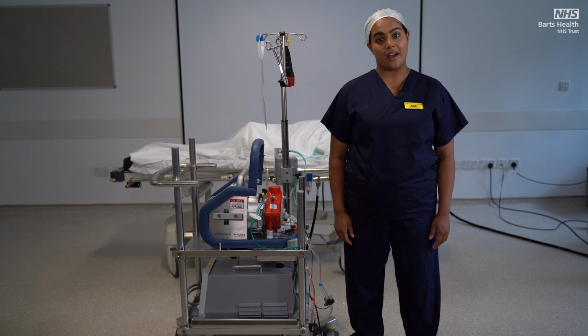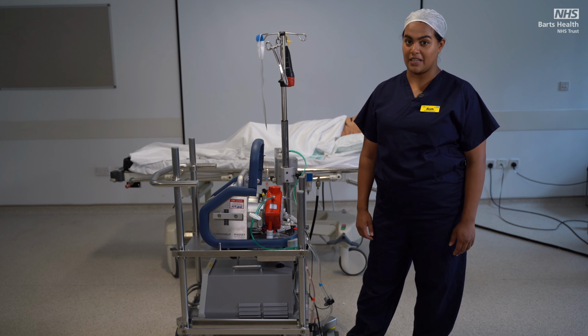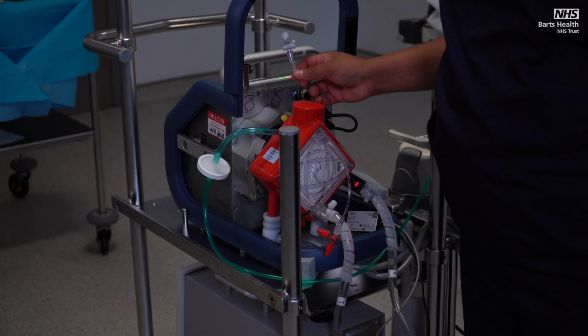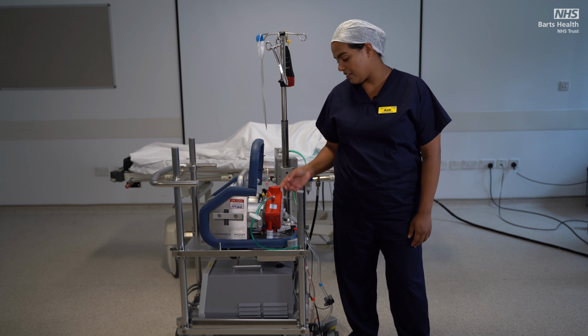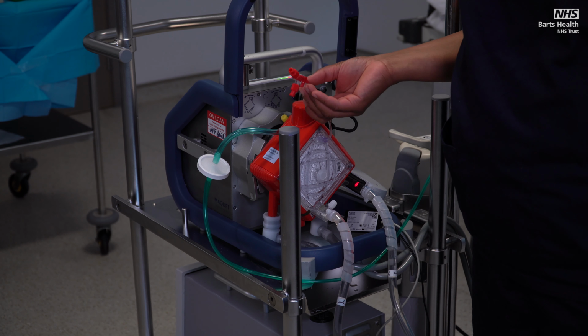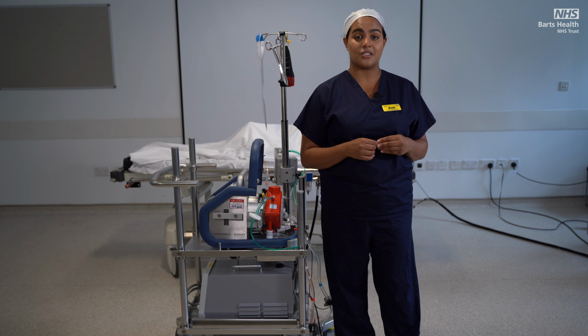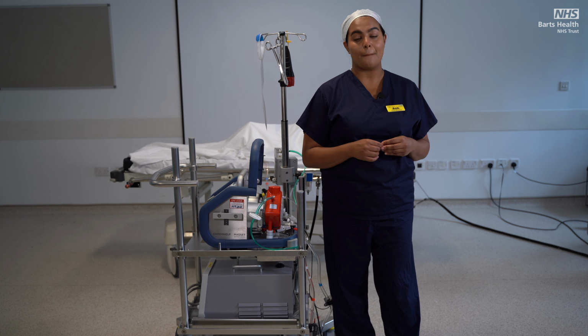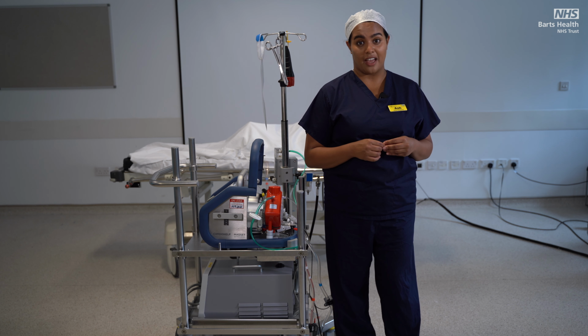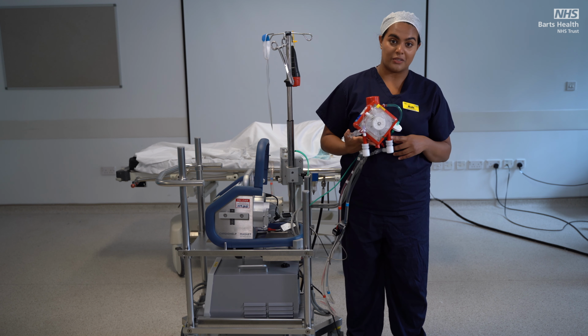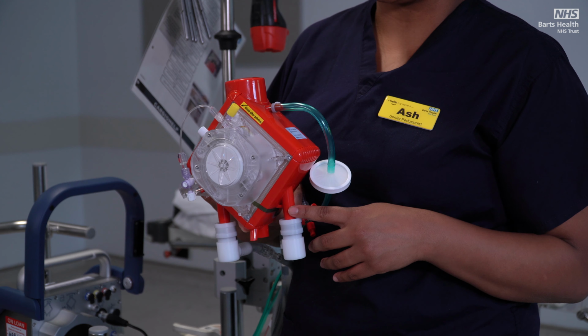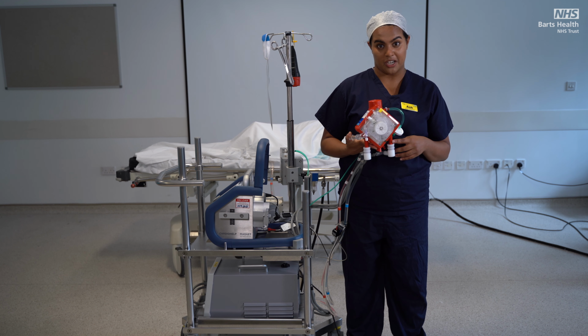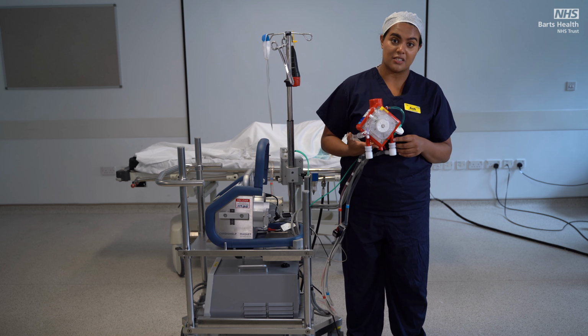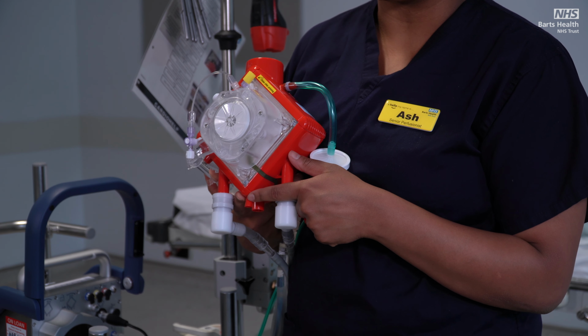There are 2 ECMO access ports on the Cardiohelp, also known as pigtails. One of them is on the pre-oxy side and the other on the top post-oxy side. These are routinely used to sample the pre- and post-oxy blood gases whilst the patient is on ECMO. They are also used in the de-airing efforts in both minor and major air. The downward-facing ports are attachments for the heater coolers to ensure that your patient is kept at the desired temperature. It's also really important to note that you should never block off or occlude the exhaust pipe.